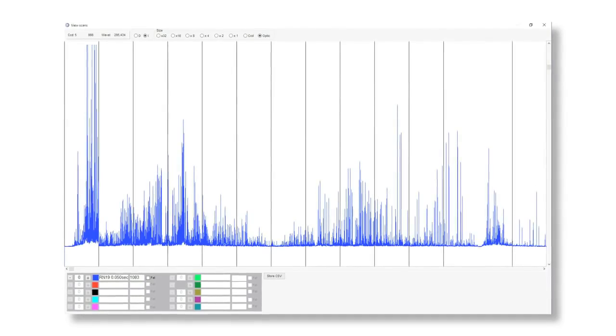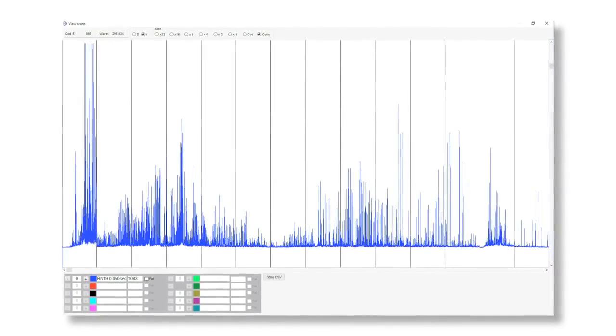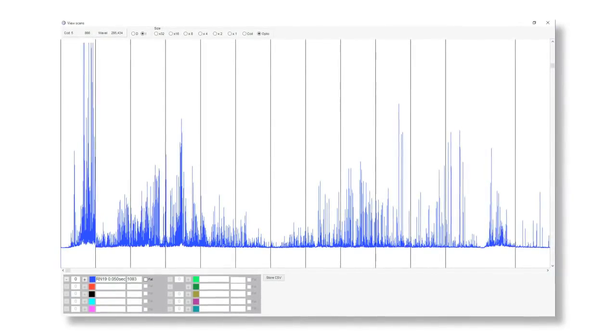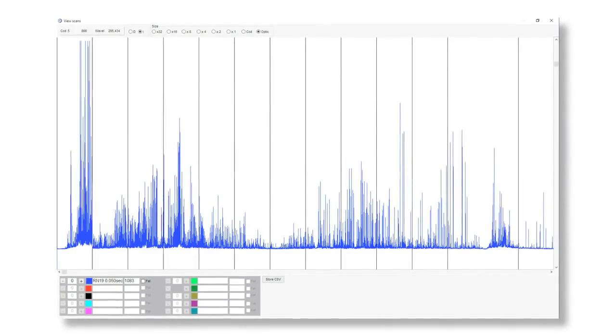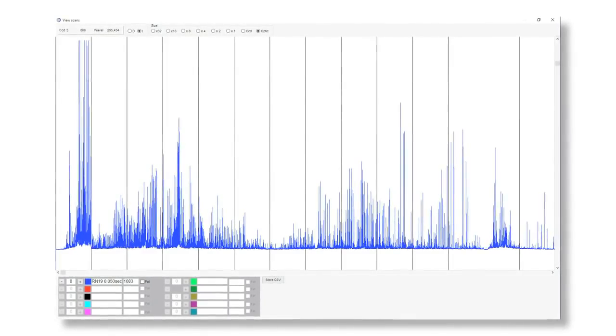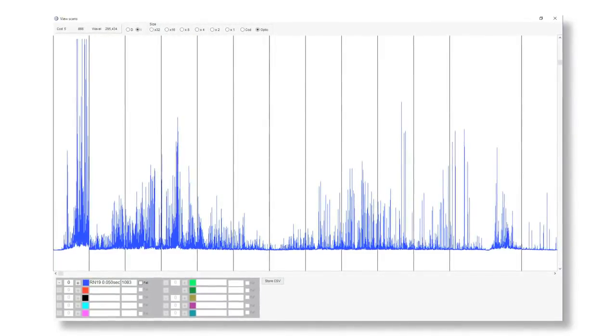For a typical metallic sample containing iron, manganese, chromium, nickel, vanadium, etc., each element emits many wavelengths, leading to a line-rich spectrum. For example, iron emits just over 8,000 different wavelengths, so choosing the optimum emission line for a given element in a sample is important.